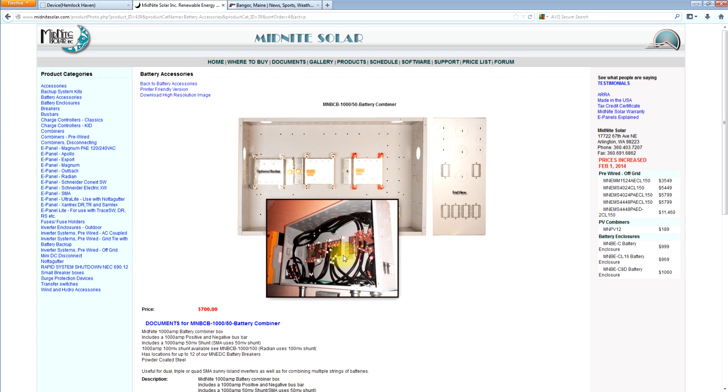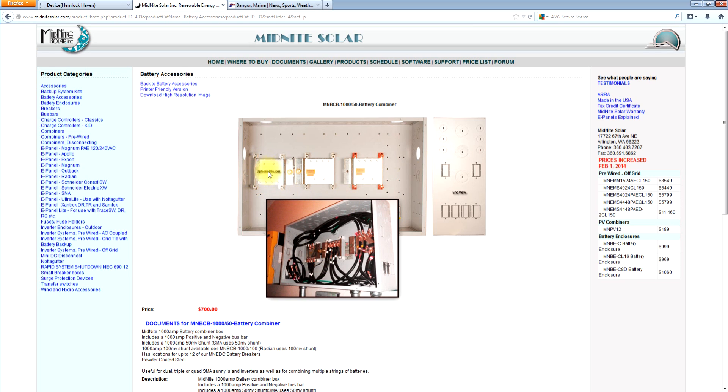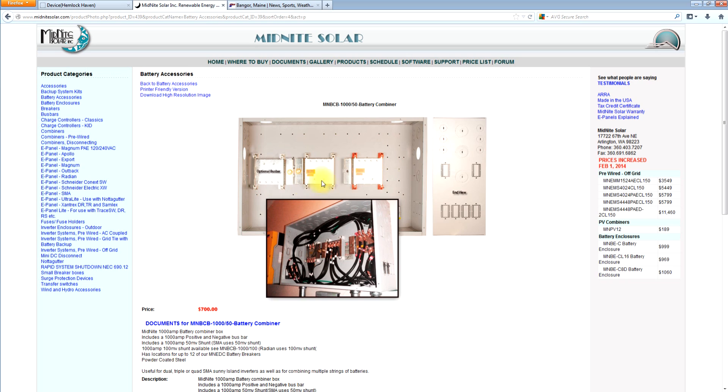As you see here, this is a really nice installation done. And you can see that they've actually double lugged the lugs. So they actually put two lugs on each stud, which gives you a lot of attachment points. You could actually drill the copper bus bars and use stainless hardware and bolt the lugs on as well if need be. But these are 1000 amp rated bus bars. And this box is plenty big for bending room.